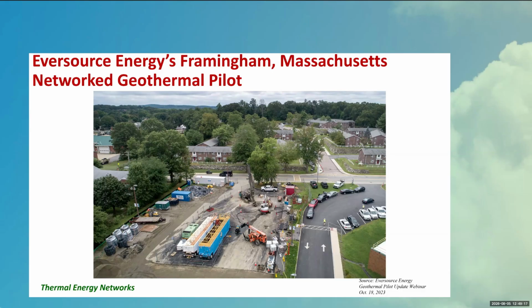The other most important factor is diversity of load. If you're going to build a huge network of systems and they're all heating dominated, they're not actually helping each other, they're just making that loop colder, so there's no real benefit to connecting them. You'd actually get more benefit out of putting in boreholes that just serve each building individually, because the cost to connect them, build pumping stations, and manifold everything ends up dramatically increasing the cost to convert those buildings.